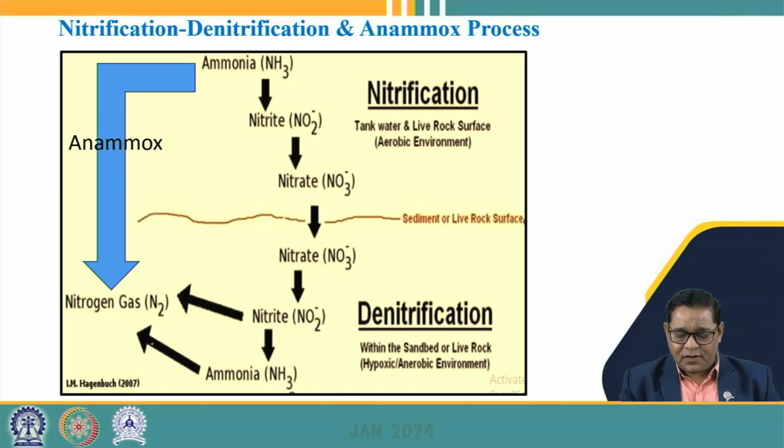This process of nitrification and denitrification is mostly used in removal of ammoniacal nitrogen present in the wastewater in sequence, so that ammonia nitrogen is first nitrified to the form of nitrate, and then this nitrate becomes the substrate for denitrifying bacteria which are present in the wastewater, and in anaerobic conditions they are finally converted into nitrite, ammonia nitrogen, and then finally to dinitrogen gas.